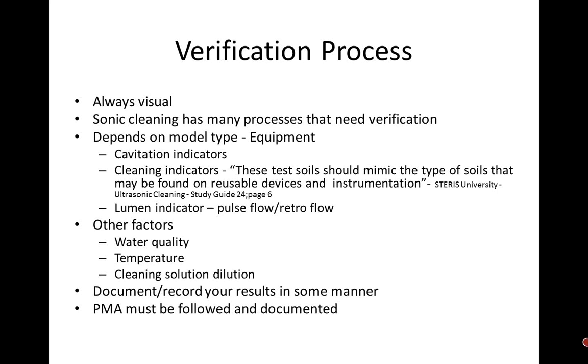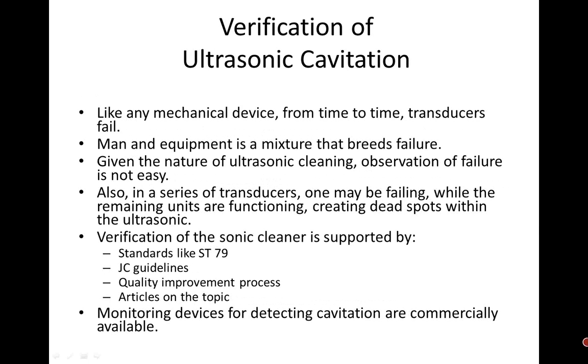The process entails a lot of things, and I hope we've started to show you the importance of it. And you might want to check water temperature, your cleaning solution dilution, also testing: does it clean and does it have cavitation, but also make sure your preventive maintenance is being followed. Also, again, the standards support this. There are articles that support it. Transducers do fail. I've given you some examples. Pulse flows fail, not only the pump, but the connectors. And if you don't check it on a regular basis, you are going to have issues.